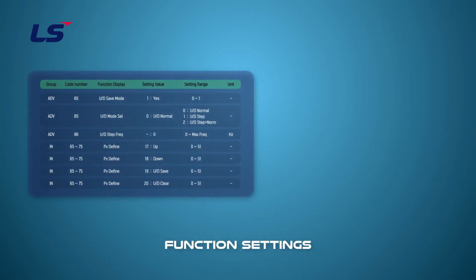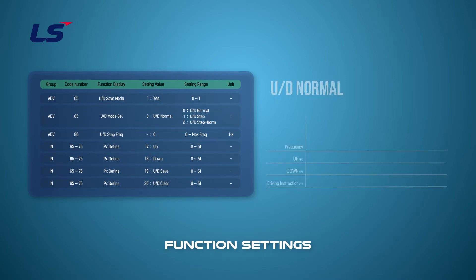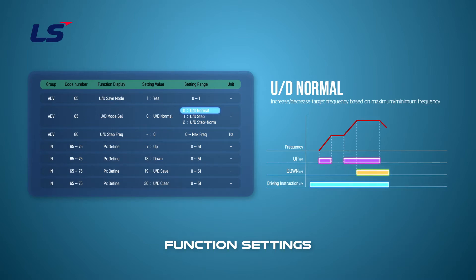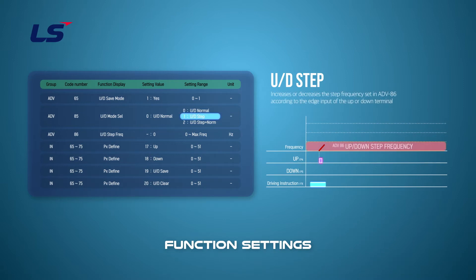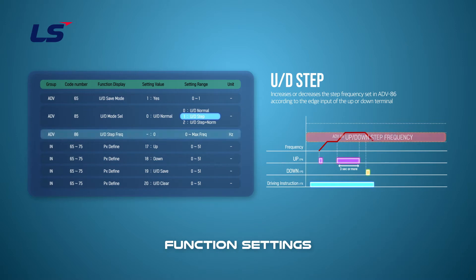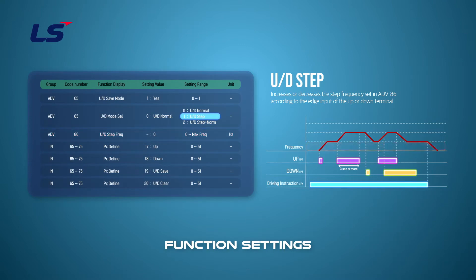Next, let's take a look at three operation modes of the Up-Down function. The first mode is Normal mode, which accelerates when the Up digital input is on and decelerates when the Down is on. The second mode is Step mode, which accelerates or decelerates by the frequency programmed in the Up-Down step frequency parameter, ADV 86.